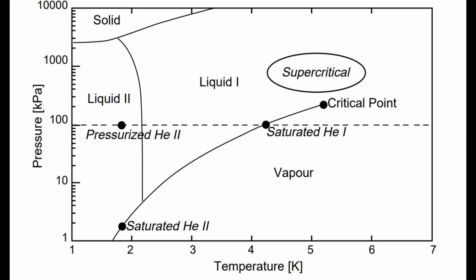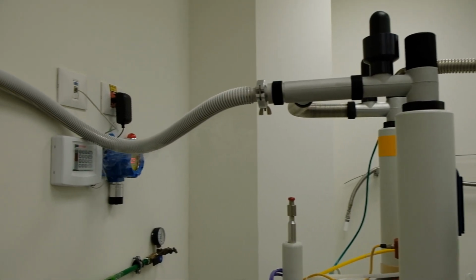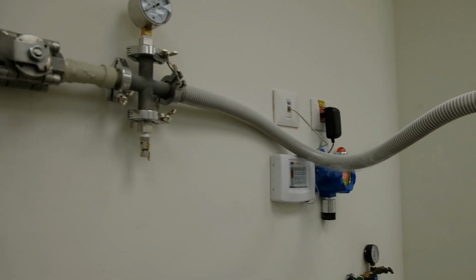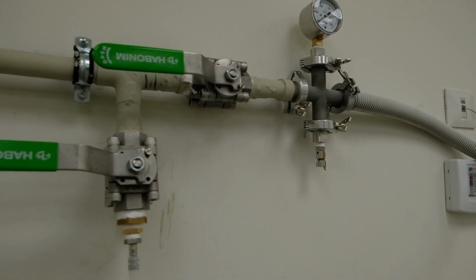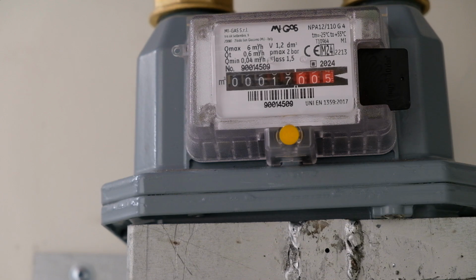The source of helium is an NMR magnet. This must be kept at 4.2 Kelvin, otherwise the magnet will lose superconductivity and quench. The boiling point of helium increases by about 0.12 Kelvin with every 100 millibar of pressure, so any recovery system must minimize back pressure. To prevent problems, an overpressure relief valve is needed. The helium leaves the magnet via a one-way valve and goes through a gas meter and pipework to collection bags.